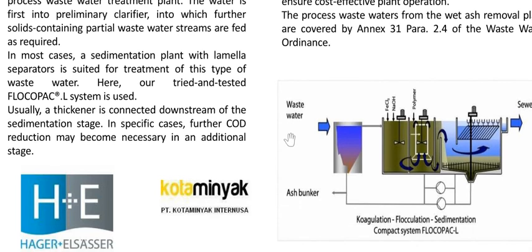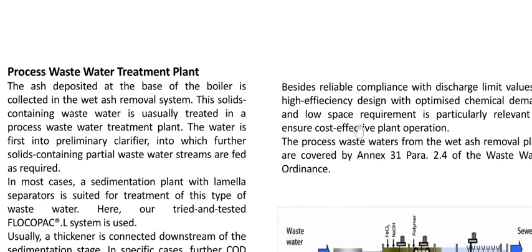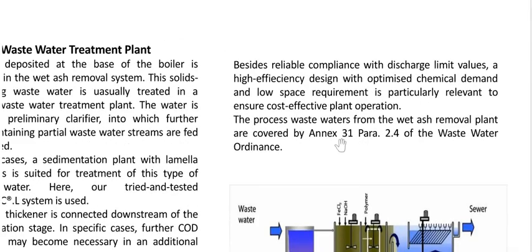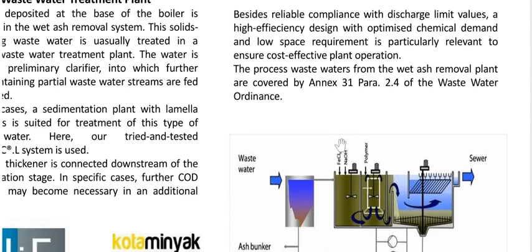Usually, a thickener is connected downstream of the sedimentation stage. In specific cases, further COD reduction may become necessary in additional stages. Besides reliable compliance with discharge limit values, a high-efficiency design with optimized chemical demand and low space requirement is particularly relevant to ensure cost-effective plant operation. The processed wastewater from the wet ash removal plants is covered by Annex 31, Para 2.4 of the Wastewater Ordinance.